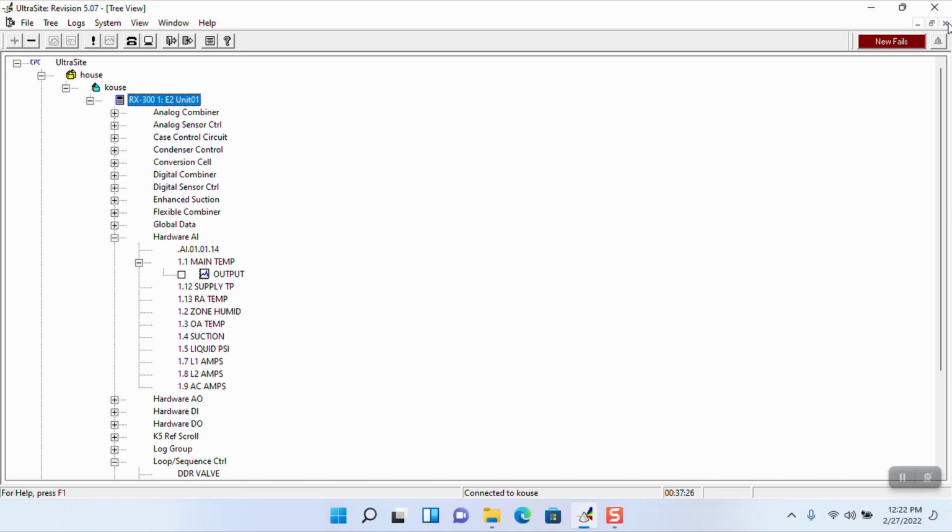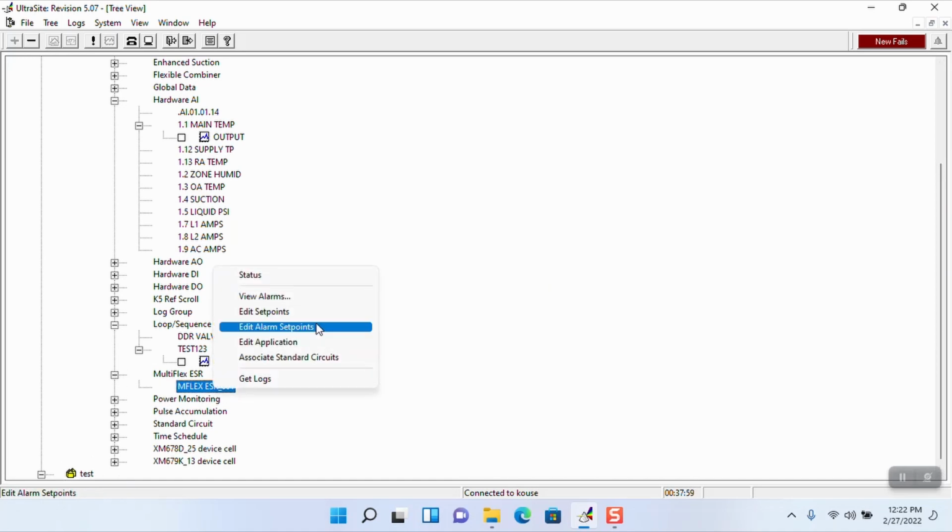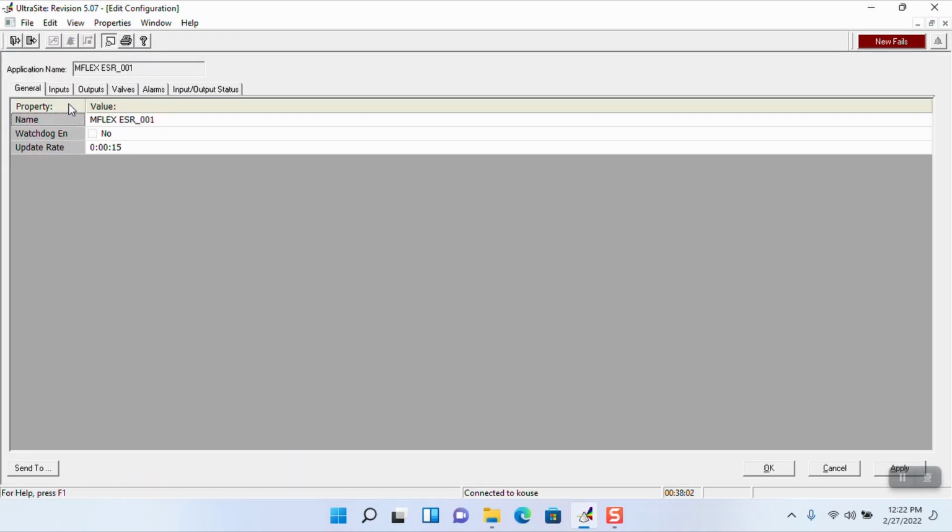But that is a basic loop sequence control. Like I said, a lot of this is custom. I've done custom drive stuff with it. I've done my own pump skid control with it. I've done heaters with it. I've done defrost differential valves, holdback valves, receiver pressurization valves, dampers, anything that's going to be variable and it's going to be outputting a variable output, meaning a percentage. You could tie it to ESR points. You could tie it to the ESR points as an input.